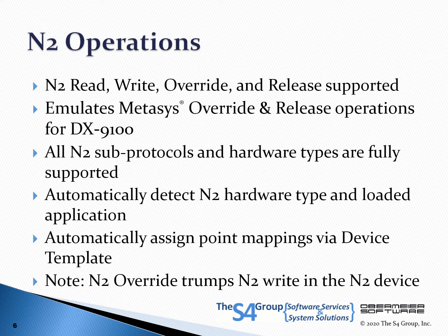N2 read, write, override, and release operations are supported through BACnet. When an N2 point is in override, the N2 device will accept and acknowledge the receipt of a N2 write request. However, the value of the write request will be ignored by the N2 device. You can submit multiple N2 override requests against the N2 point. Each one will replace the value from previous overrides. An N2 point can be put back to normal operation with a N2 release command.